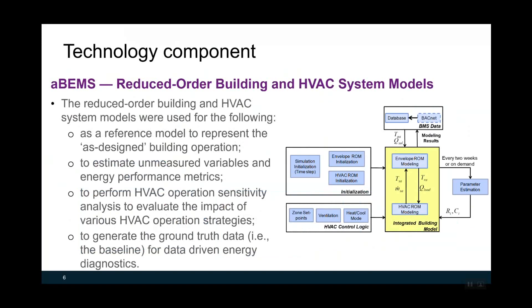The reduced order model was used for the following purposes. First, we can use the reduced model as a reference model to represent as-designed building operation. It can also be used to estimate unmeasured variables and energy performance metrics. We can also use the reduced model to perform HVAC operation sensitivity analysis to evaluate the impact of various HVAC operation strategies — essentially conducting if-then analysis. Finally, the reduced model is used to generate ground truth data for data-driven energy diagnostics. The figure on this slide shows the coupling procedure between the building envelope reduced model and the HVAC reduced model, along with HVAC control logics.